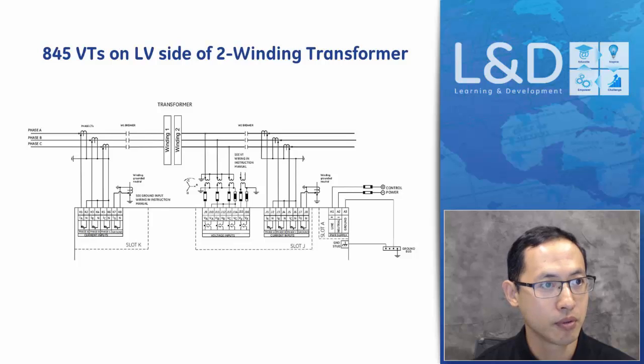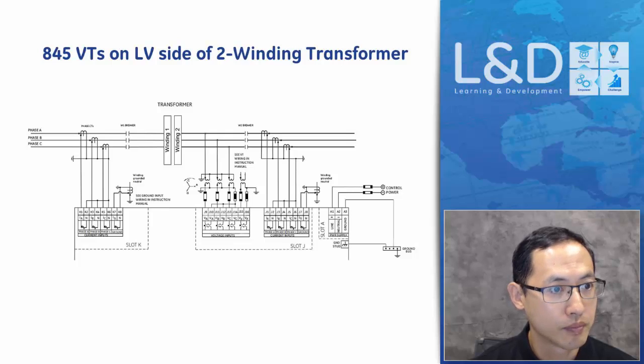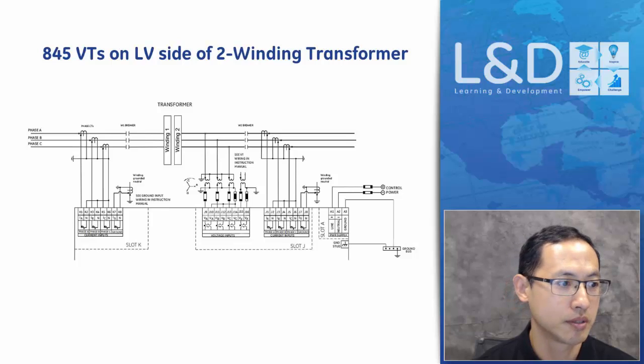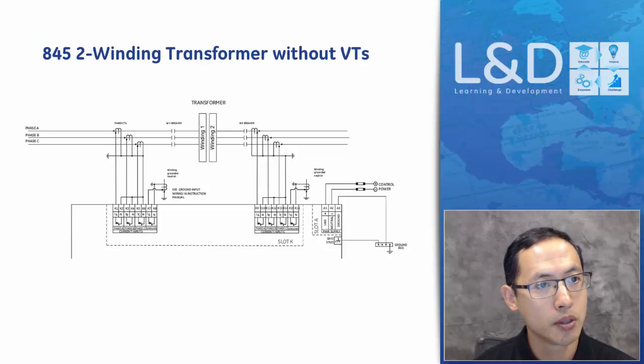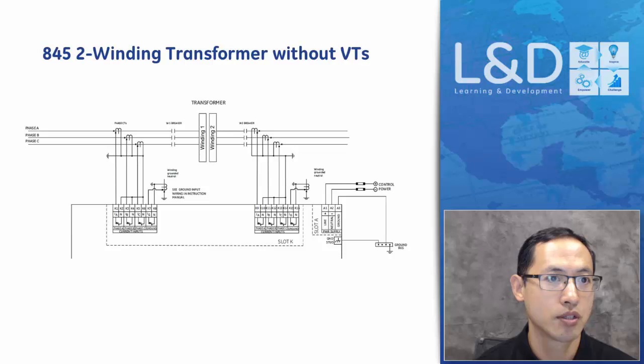And then if you want to install the VT on the low side of the transformer, then the J slot will be connected to the low side VT. So J9 to J16 is connected to the low side of the transformer. There's another option in the order code to choose an 845 with only the CT inputs without VTs. So in that case, for the J and K slot, CT inputs will be used and no VT will be used.